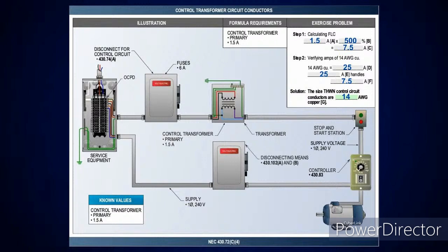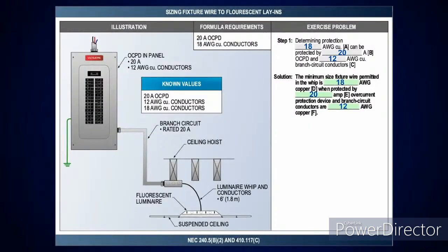And we're having problems. But anyway, here's a 20 amp overcurrent device. This is where you're going over. You've got your fluorescent lighting that's there. And we're just showing that this is a fact that determines my protection, and can the number 18 conductors be protected by a 20 amp overcurrent device? Well, sure, because your fixture wire is permitted in the whip to be number 18, and that 20 amp will protect that, plus the number 12 conductors that are going over there. And another section I would reference here is 240.4(D), which also deals with small conductors.